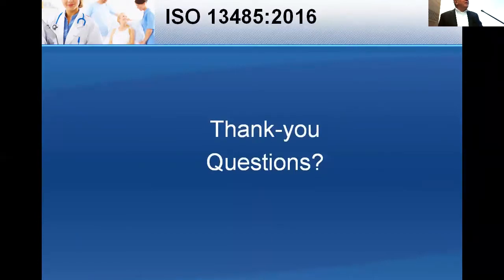The most common thing that happens for me is I get a call from a guy who's raised a potload of money and got a device that's working and ready to go to market. He calls me up and says, I talked to Health Canada and they tell me I need this thing called ISO 13485. My device is already designed, it's ready to go to market. I'm sorry, but your device is not designed in the view of the regulators. You've got to go back and redo a lot of what's probably been done for your product under some design controls. You have to go back beyond the prior iteration.